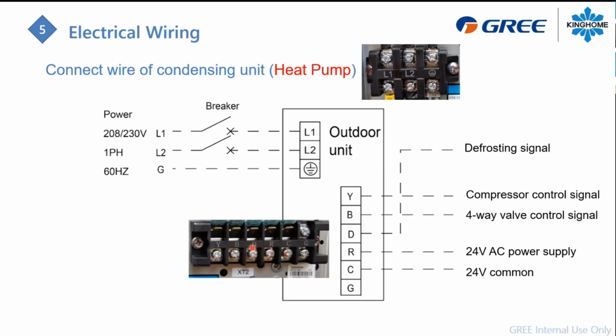The D connection right here, it's an output signal for the defrost. So in a case that you will need to enable the furnace or your duct heater during the defrost of the outdoor unit, well, you will need this D connection. In other case, if you don't want to provide heat during the defrost, because the defrost cycles are very short and you don't have to apply any heat during this time, well, the D connection is optional.